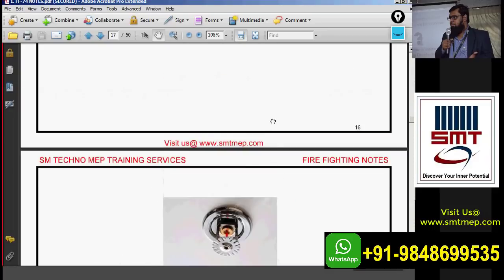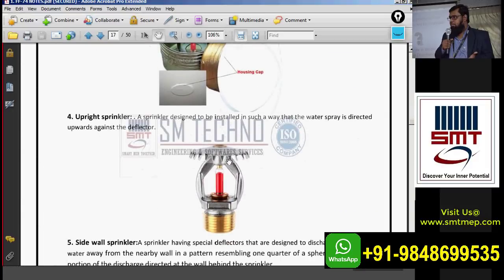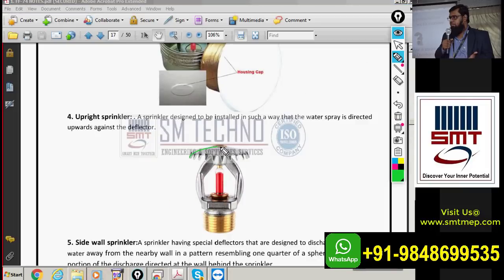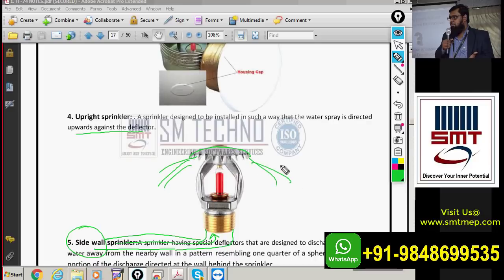Next we have the upright sprinkler. Comparing to pendant, the pendant deflector is flat and round, but the upright deflector is curved — somewhat like an umbrella. The upright installs above the pipe level, or above the false ceiling level. It is designed so that water is directed upwards against the deflector, forming a downward spray pattern.